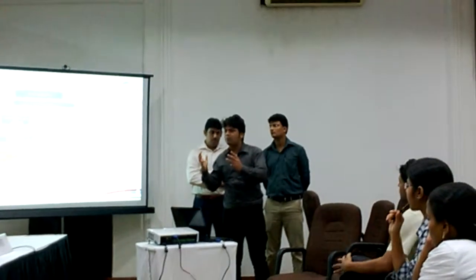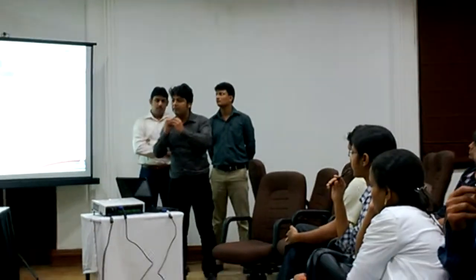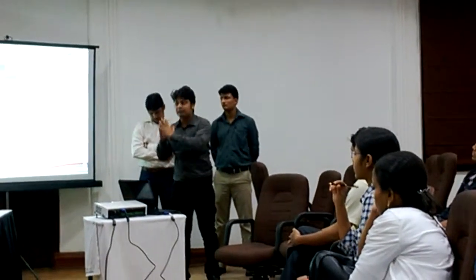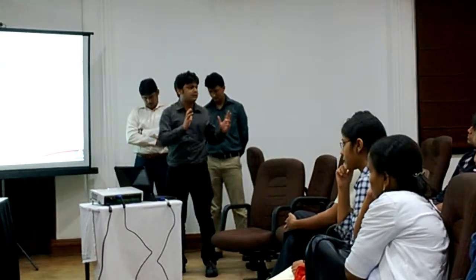After this methodical approach and a lot of brainstorming, we found some very interesting cases: the signal cable for the voltage feedback was laid along with the high voltage ignition transformer cable, and moreover there were noises and interferences due to the auxiliaries of the oxidizer.